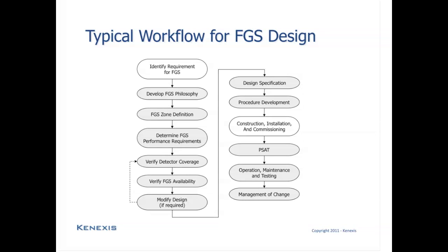After installation and commissioning has occurred, there is a validation step, or sometimes it's referred to as the pre-startup acceptance testing phase. This is where all of the functionality of the fire and gas system will be verified in terms of looking at the actual equipment, where it was installed, how it was installed, and how it was programmed to verify that the design meets the requirements of the fire and gas SRS, and also actual physical testing of the system to ensure that its performance matches what was specified in the fire and gas system SRS. After the PSAT, the system is turned over to operations and maintenance for day-to-day operation.